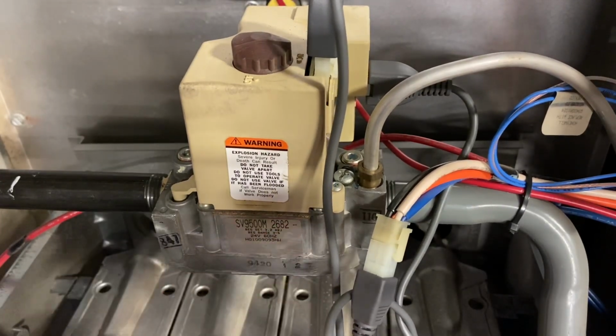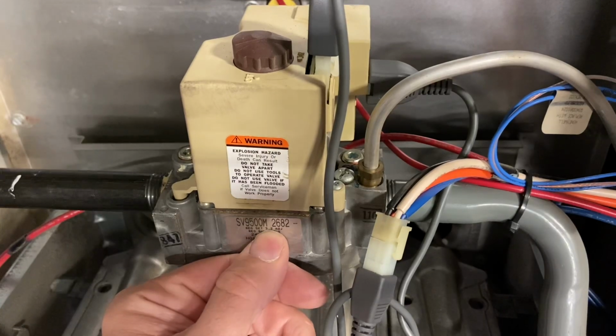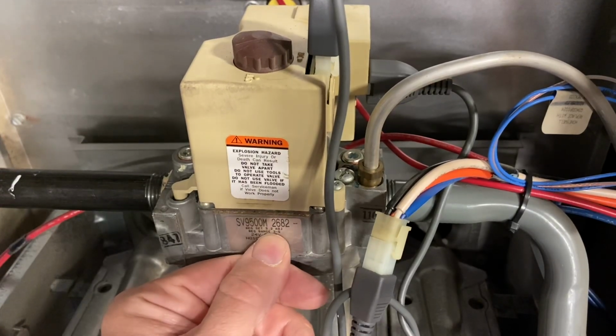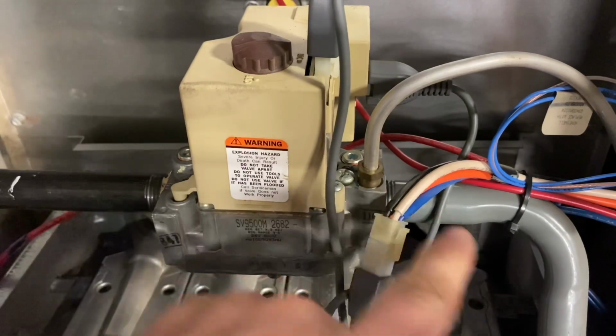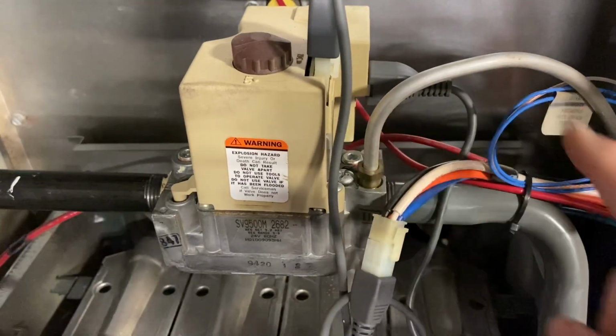valve. Actually, I stand corrected. This one is 3.2 inches of water column as a range between 3 to 5. So this is where we're going to set the manifold gas pressure. This is our pilot tube.